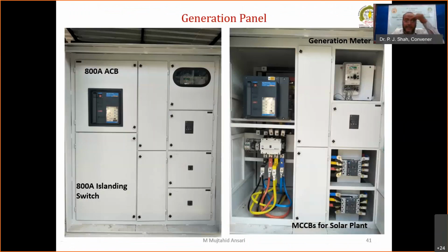Now it is the AC panel. In the AC panel, there is an 800 ampere ACB, an air circuit breaker, because no doubt we have installed the first 100 kilowatt plant. Next, a plant of 195 kilowatt is already installed. So the existing power plant is a 195 kilowatt solar PV on-grid power plant, which is working, and one more third phase of 100 kilowatt we are going to install, or it is in process.